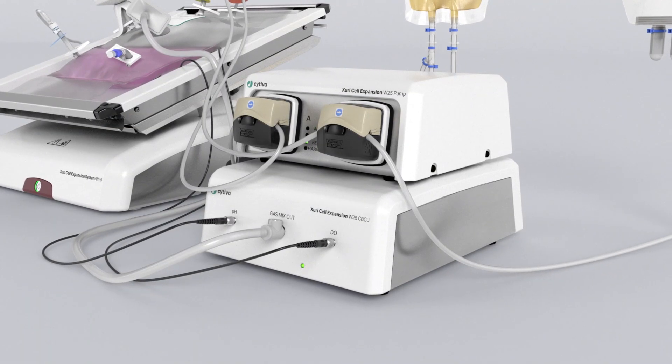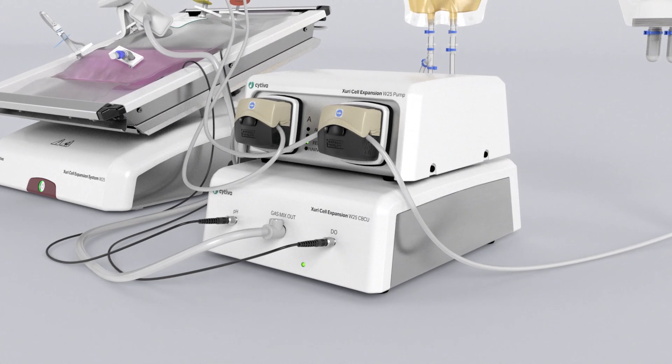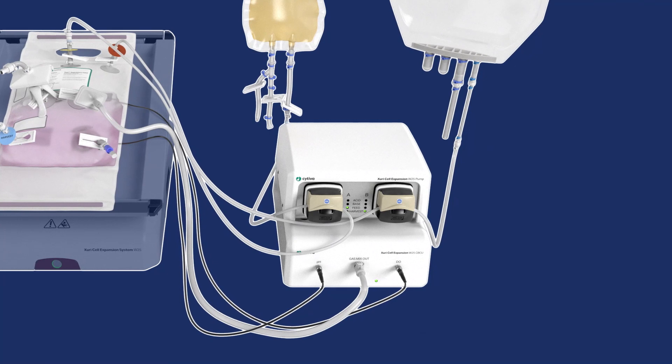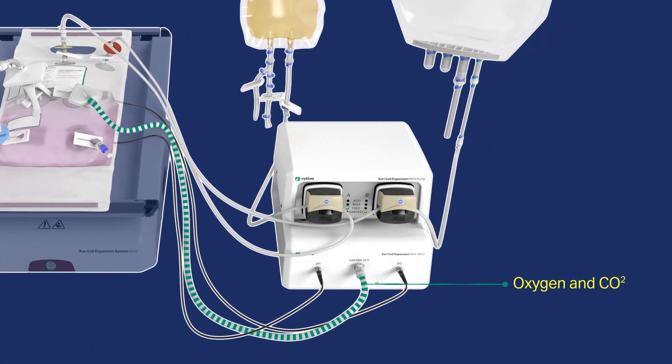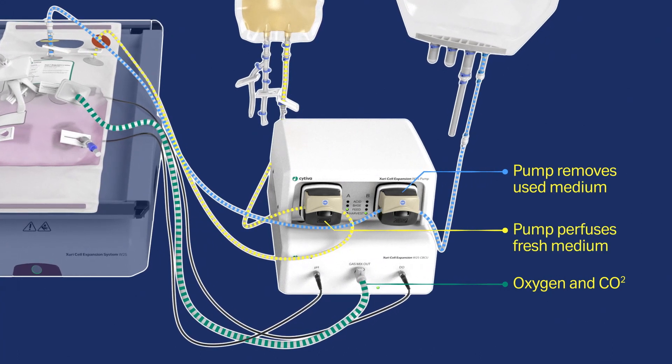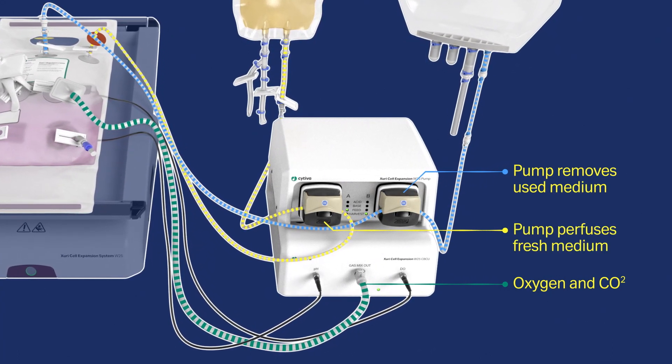The cell bag control unit, CBCU, and Xuri W25 pump control the environment in the bioreactor. The CBCU regulates how much oxygen and carbon dioxide flow into the culture, and the pump perfuses fresh medium and removes used medium.